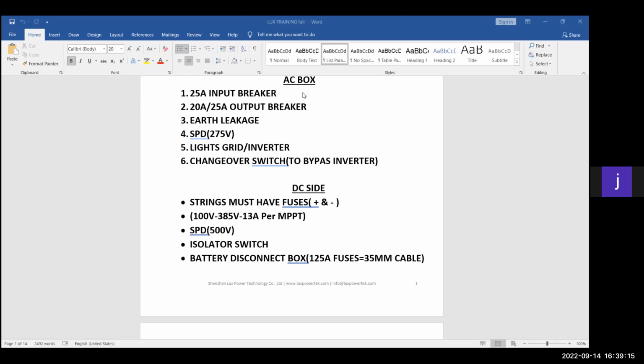Yes, I'm talking about a single inverter at this moment. I'm not talking about multiple inverters. So all this is per inverter. I'll get to the parallel setup slightly further down in the training manual, where I give all the breakers that I recommend for parallel systems and so forth. So this is just the recommendations that we have for you to try to protect the machine. Then, as well as an SPD, South Africa's grid is extremely unstable and we have a lot of spikes from Eskom side on the inverter. So an SPD to protect your system against a big spike.